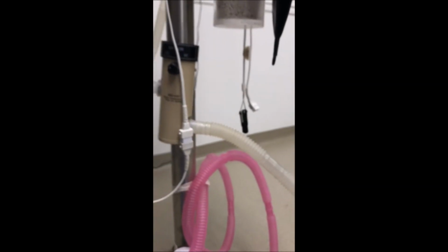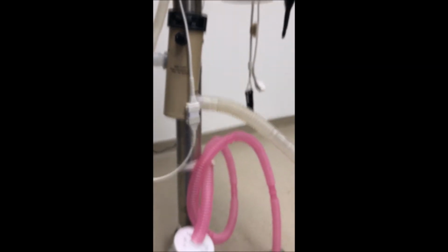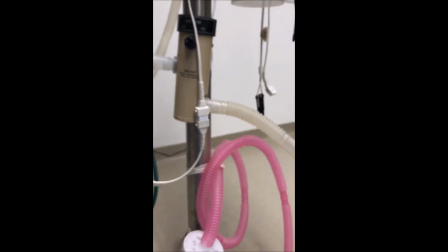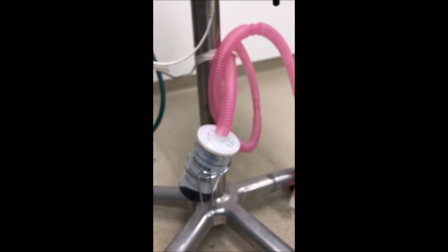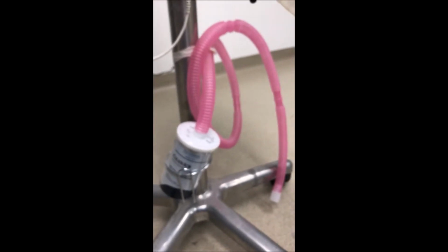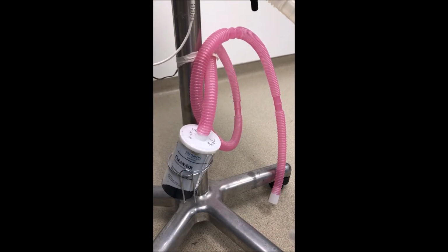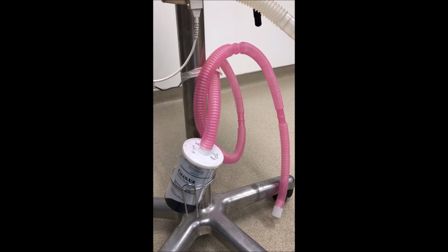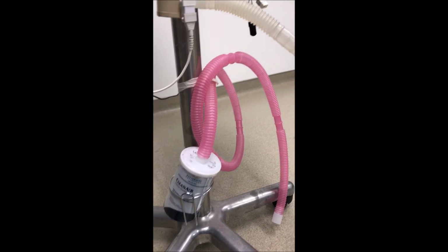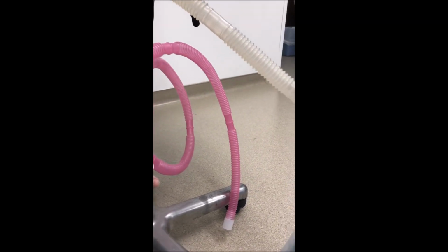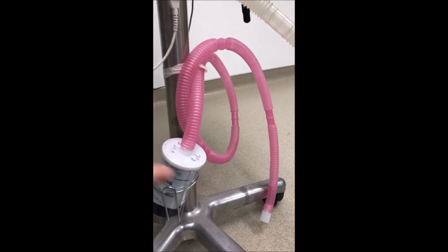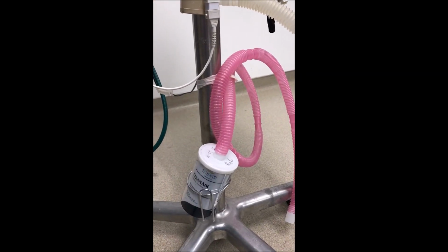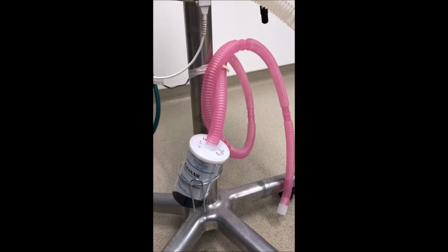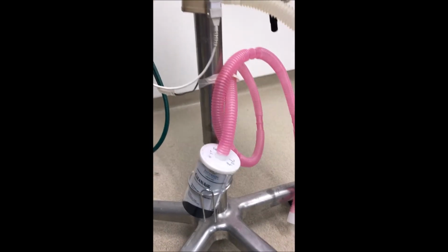Now, in our x-ray room, depending on where our anesthesia machine sits, we may not be able to reach the exhaust there. So we also have a passive exhaust system here. Let me focus in, there we go. So if we were in an area that we did not have proper exhaust hooked up, then we would replace this and connect everything for this passive. If we use our passive exhaust instead, we need to ensure that we replace it so that it always works properly for us.